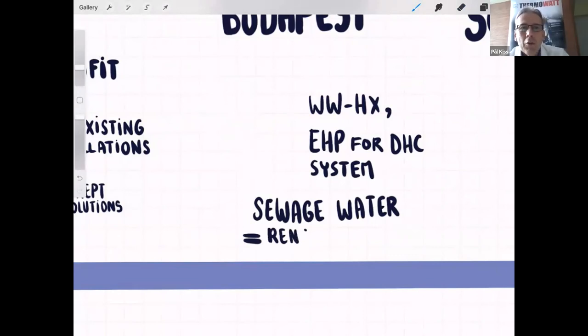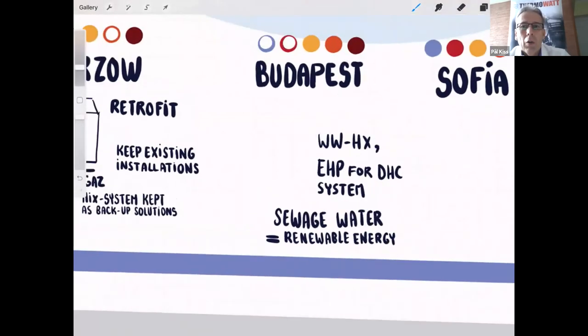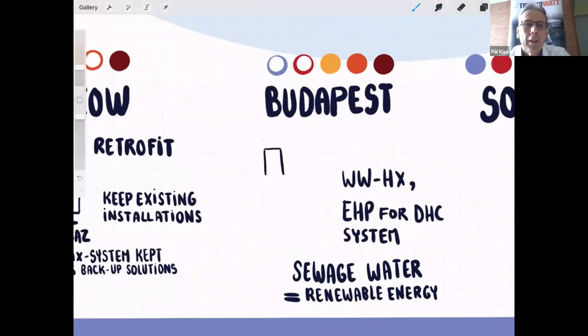Yes, our site is a bit special one, having a very old building and a completely new one. The main interesting challenge was to harmonize those inner systems of the buildings. And also, as far as the end users are different, the heat demand in terms of temperature is also different. So radiators need higher temperatures, whereas in the New Market Hall we could provide lower temperatures. So that was an important challenge. And there was an operating city center around where we had to work. So we made our installations with a very low disturbance of our environment. It was very important also.